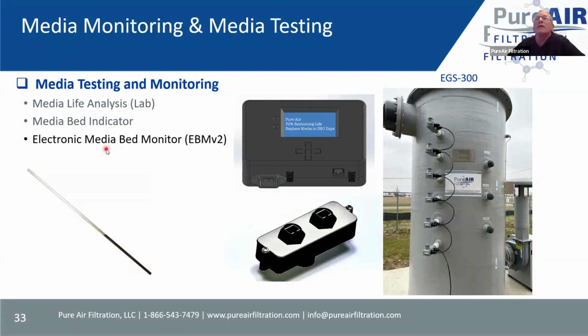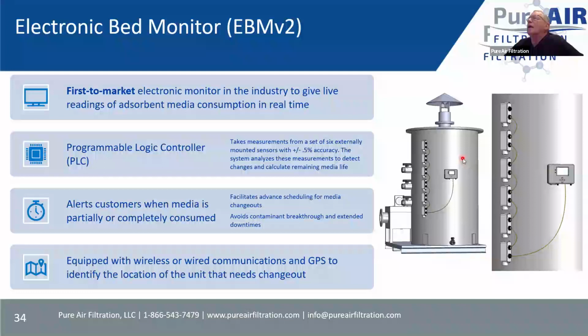And we also have our electronic media bed monitor, our EBM, which you can see here. You have different sensors. The sensors are going to sense the media as it expires. Basically, the chlorine will come in from the top and it expires in bands.